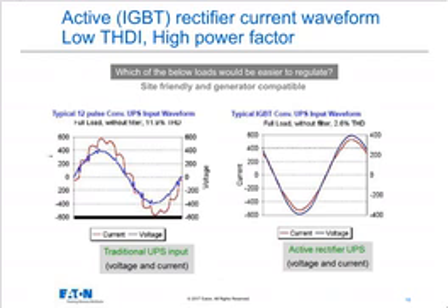And while we're forcing that current to be as sine wave shaped as possible, we also aligned that input current, the red waveform here, along with the voltage, so that the power factor, which is the cosine of the phase difference between the two, in this case, the difference between the two is 0, and cosine of 0 is 1. So that's how you get the high input power factor that you see on modern UPSs today.